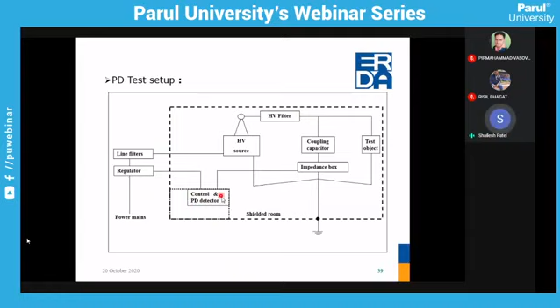It is a combination of inductor and capacitor. This one is the coupling capacitor. From there we take the return path for the PD measurement, and this is the test object, that is our cable, and this is the PD detector. This is the basic construction of cables. In laboratory conditions for PD measurement, this is the bare condition of the 11 kV cable, and here you can see the conductor.